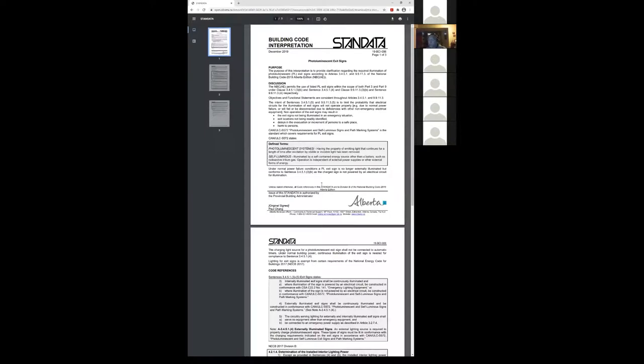because typically this didn't address the fact that there are photoluminescent exit signs. Before, if you just had a paper or plastic exit sign, you had to have that lit up to see the exit. Now with photoluminescent exit signs, they are energized by a lighting source. And when the normal power goes out, they don't need another light to activate that sign. Now that sign has to be a listed sign and certified for the time frame that the sign will stay luminescent for the area that you need it, whether it's 1 or 2 hours and so forth, and you don't need an emergency light on that sign because the sign is photoluminescent. And somebody said, well, after 2 hours, when the sign is no longer glowing, what do you do? And it's like, you shouldn't be in the building.